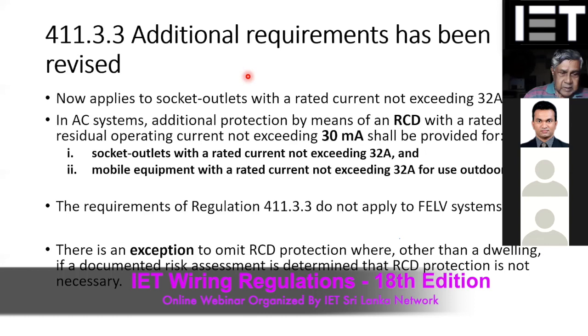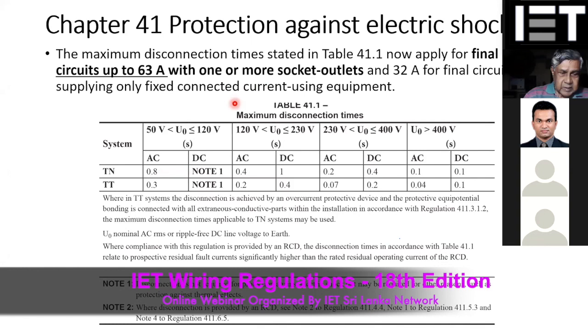And also there are certain omissions. RCD omissions are also included in the regulation, so that is an additional part where we can omit certain RCDs in some other locations. And also there is a major change in the tripping time of the RCD. When you look at the earlier version, the tripping times were subdivided into two categories: circuits less than 32 ampere and circuits more than 32 ampere.